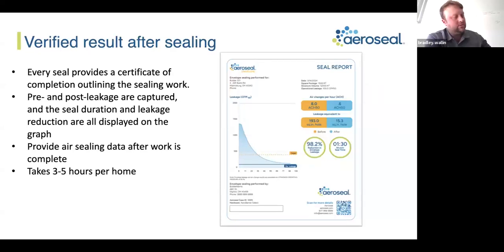We set up the system. It starts at, for example, this house started at 8 ACH50, and within an hour and a half we had it down to 0.6. In real time, every 10 seconds you're getting a reading. If there's an issue, our guys can go in, and if there's a big hole or something, they'll shoot it with a little can foam, and before you know it you're down to a really tight air level. So it's that report.